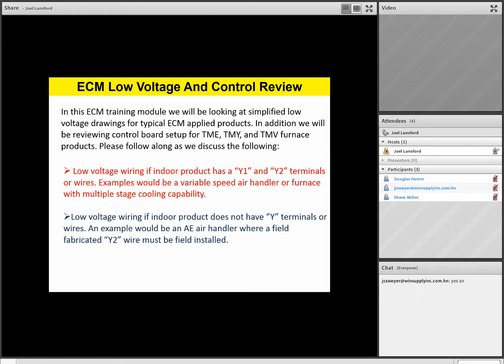Now, one of the highlights we're going to talk about is low voltage wiring if the indoor product has a Y1 and Y2 terminal. So let's give an example of that. Let's say you have a variable speed air handler, or you have a TM9E furnace, for instance, or a TM9Y furnace. You're going to have a Y1 and a Y2 terminal. So if you've got a Y1 and Y2 terminal, we'll talk about how to utilize those terminals, especially if you've got like a two-stage outdoor product.